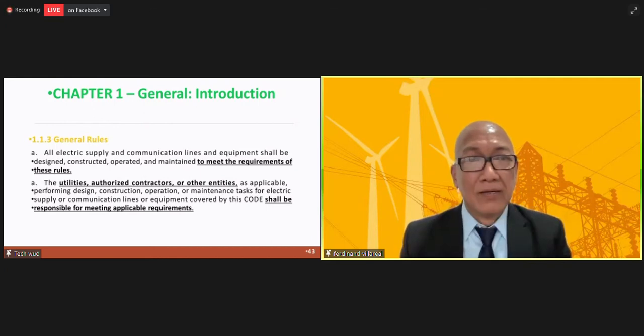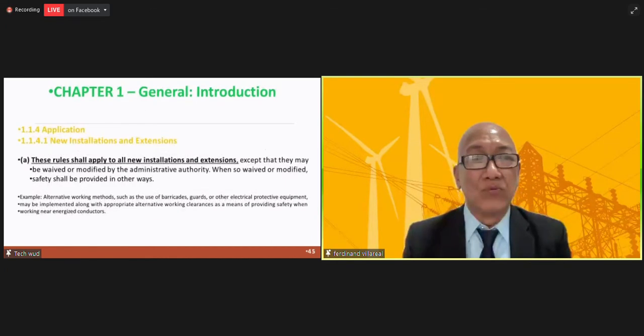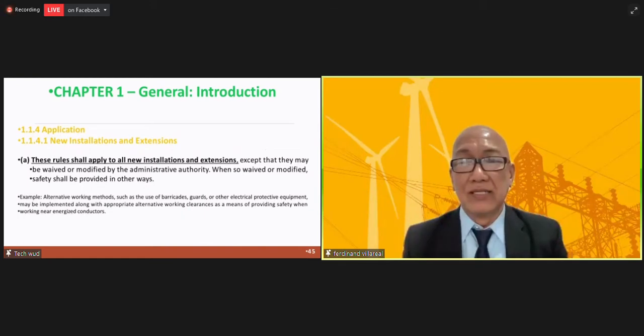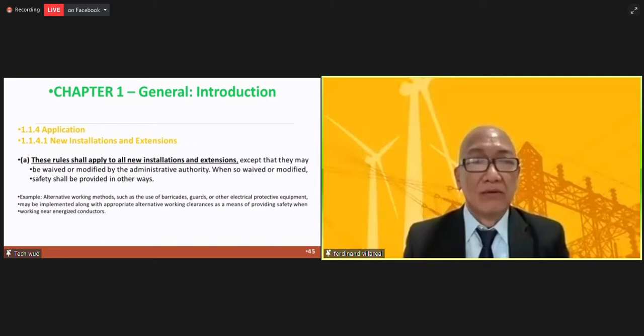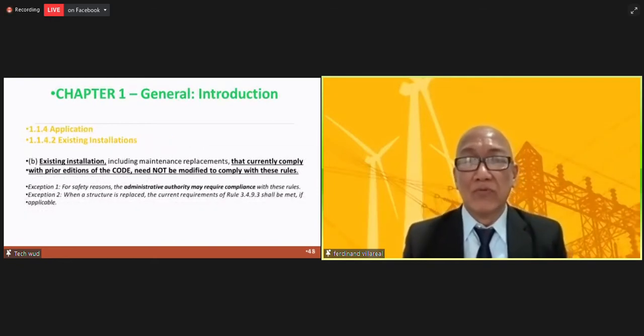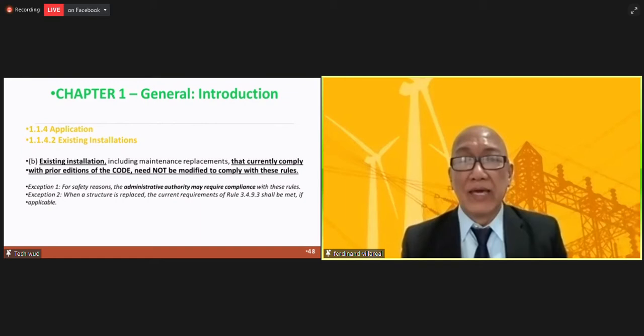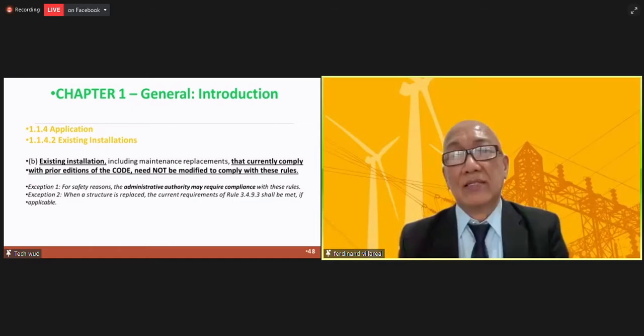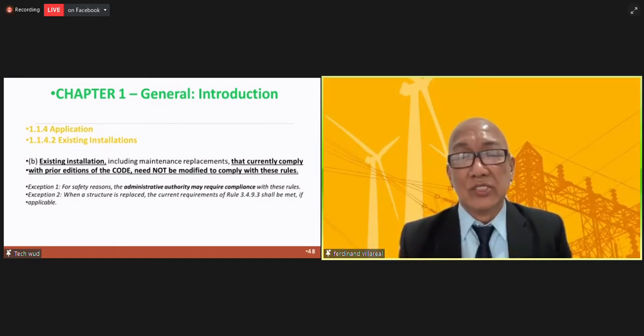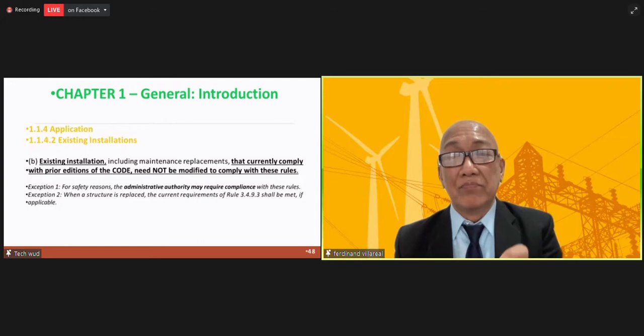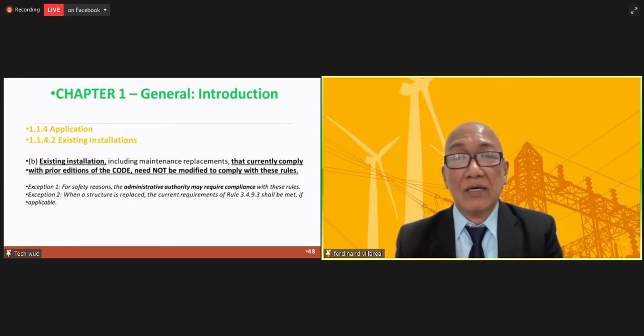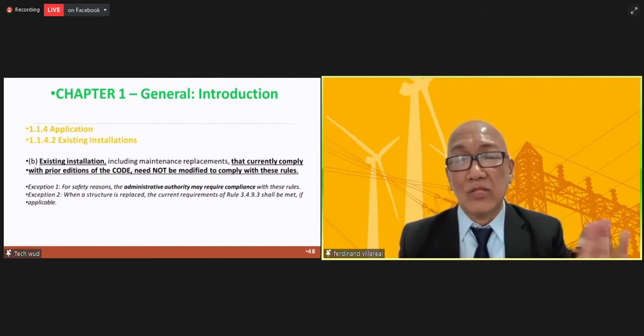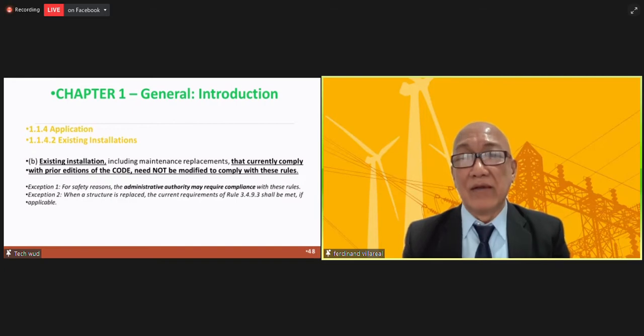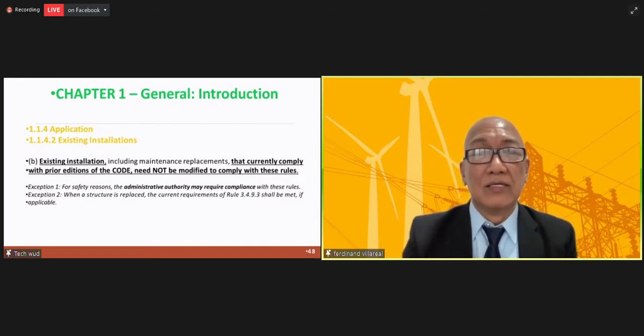For existing installations where conductors or equipment are added, altered, or replaced on an existing structure, the resulting installation will still be in compliance with the rules that were in effect at the time of the original installation. For example, if you built a line in 2008 and you just added something, replaced something, you don't need to upgrade it to the 2020 standard - whatever was in effect at that time of the original installation is what you follow.